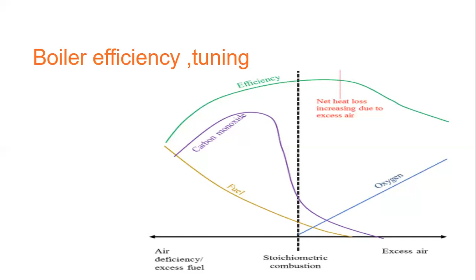You need to periodically make a performance evaluation and compare the results obtained during the test program. So this is called boiler tuning, a very important step in improving the boiler efficiency. As I said, we need to reduce the excess air and operate the boiler to come out with the solution where there is the lowest practical oxygen level. When I say lowest practical oxygen level, we need to take care of the smoke, CO and stack temperature, and we need to maintain caution that extremely low excess air could be catastrophic. So we should achieve both things: safe operation of the boiler as well as efficient operation.